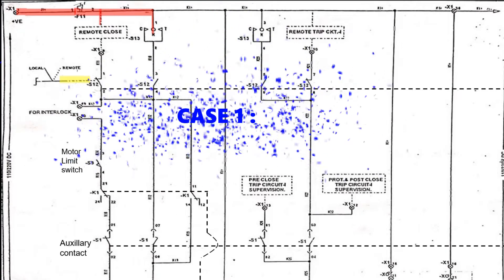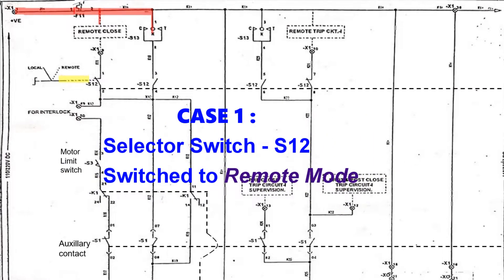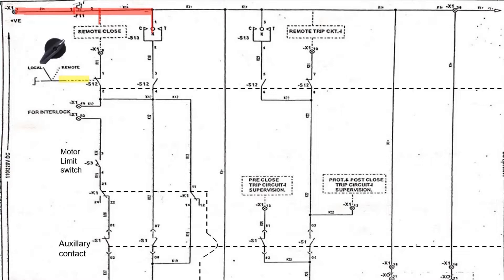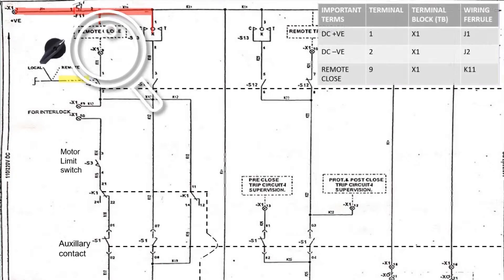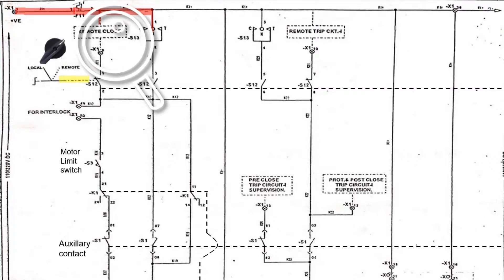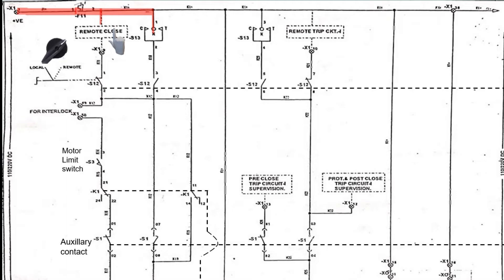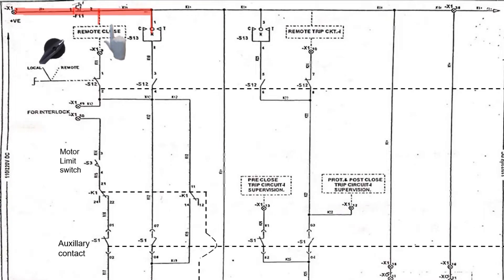Let us consider Case 1 where the selector switch S12 is connected or selected in remote mode. The contacts of S12 in remote mode will be in the position as shown here. Remote close is given at terminal 9 of the X1 terminal block. In remote mode, the selector switch is selected in remote, and at the panel end or in the control room where the panel is placed, the operator operates the switch and performs the closing operation of the circuit breaker.